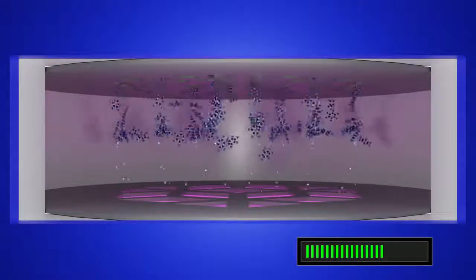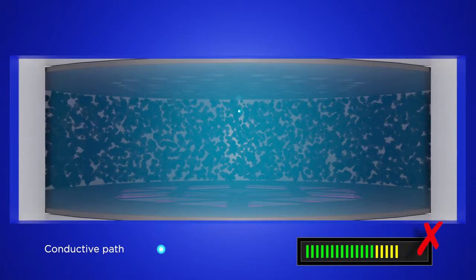Unfortunately, standard photoionization sensors have issues. If the sensor chamber becomes contaminated with airborne dirt, ambient humidity can moisten the contamination, creating a conductive path between the electrodes. This conductive path causes an artificial signal that varies with humidity.